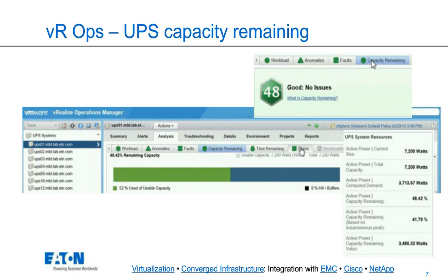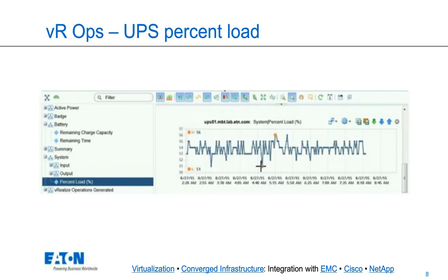On the next slide, what I'm showing is percent load. The percent load is what percentage of your UPS total power is used at any point in time. And you can see that we continue sampling these. This was August 23rd at 2 in the morning through 8:45 in the morning. You see that we averaged in the mid-50s of percent load, but we did log a low and a high during the time, the low being 51% and the high being 56%.